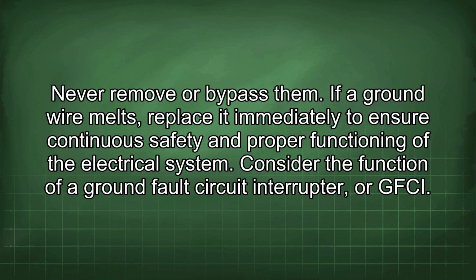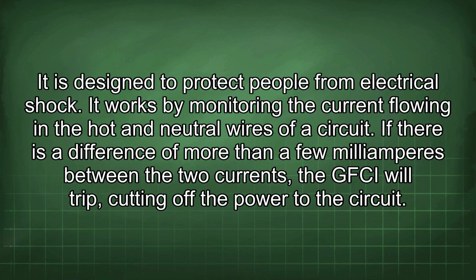Consider the function of a ground fault circuit interrupter, or GFCI. It is designed to protect people from electrical shock. It works by monitoring the current flowing in the hot and neutral wires of a circuit. If there is a difference of more than a few milliamperes between the two currents, the GFCI will trip, cutting off the power to the circuit.